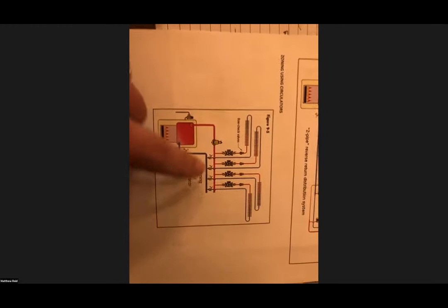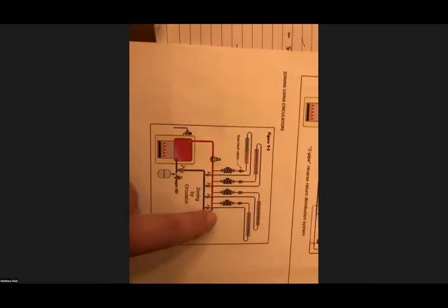Now, this gets into a much more common system that we're seeing out there in the industry. This is called a branch header system, where we have our supply branch and our return branch. We go out into our system, each zone has its own pump, goes into whatever our heat load is, and then comes back into its own common return. You see the supply and the return never touch on these. So you can't use this with all boilers. Some boilers require a primary secondary where the boiler has to get its own flow. But for a standard high mass boiler, where it's going to get lots of water on the inside anyway, this is a great way to do it.